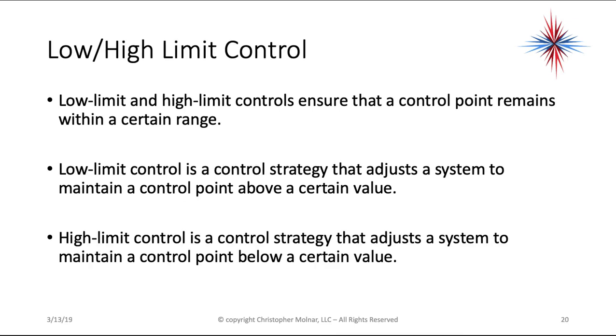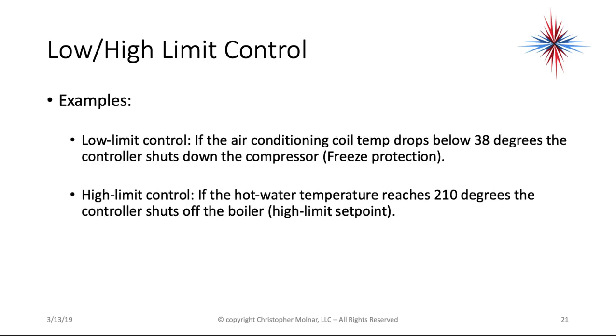Low-limit and high-limit control ensures that a control point remains within a certain range. Low-limit control adjusts the system to maintain a control point above a certain value — for example, if an AC coil temperature drops below 38 degrees, the controller shuts down the compressor (freeze protection). High-limit control maintains a control point below a certain value — for example, if hot water temperature reaches 210 degrees, the controller shuts off the boiler. High and low limit control are part of everyday systems.